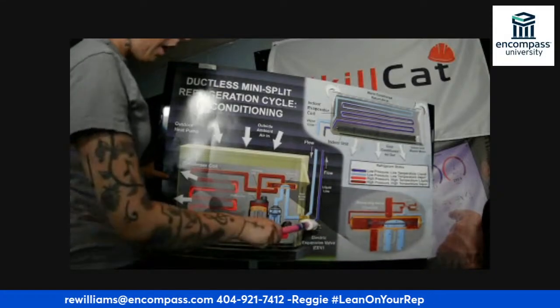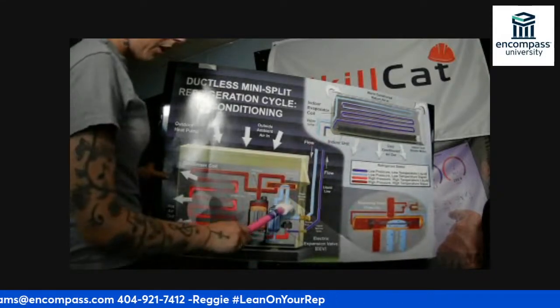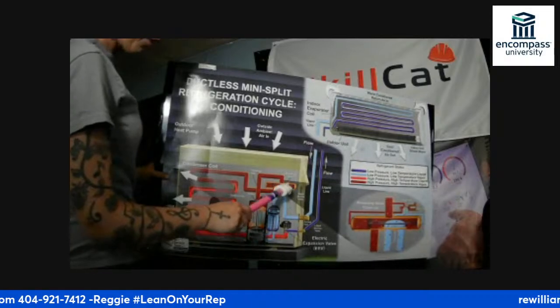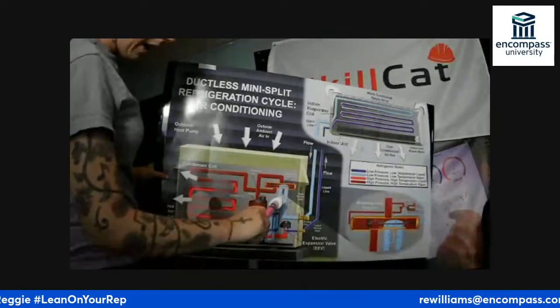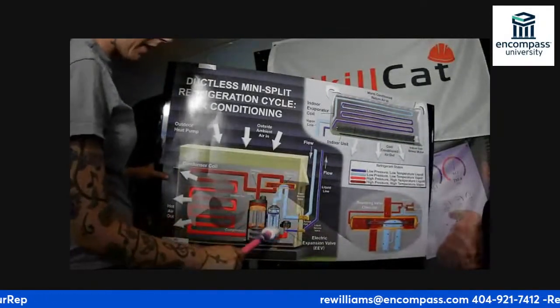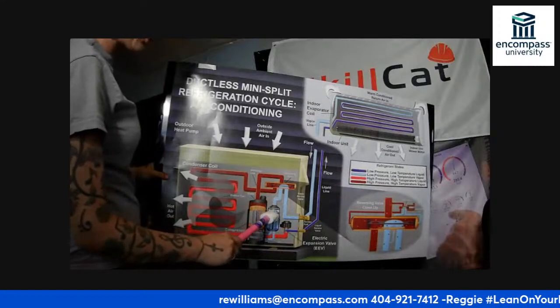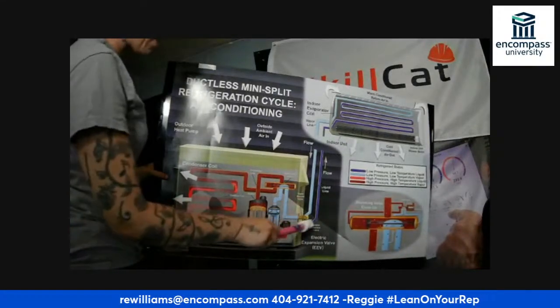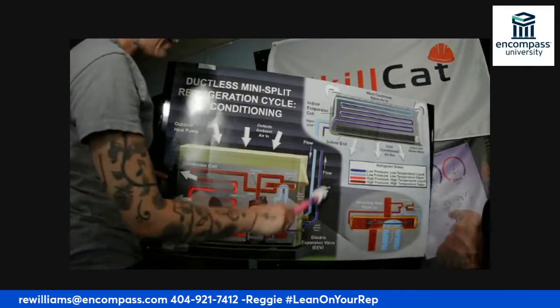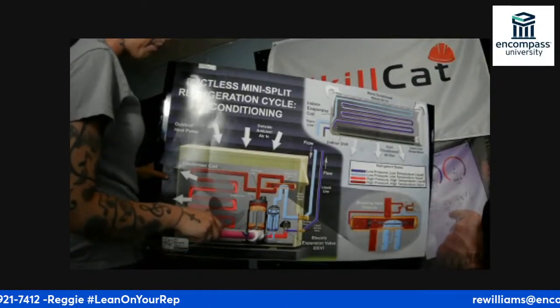So you're going to travel from the evaporator into the outdoor unit through the reversing valve. And then if we're in straight cool, it's going to come into the accumulator as that low pressure, low temperature vapor. Oh, we're coming out that way. Sorry, we're coming in this way. Okay, so when we're coming in, we're going to go to the compressor as a vapor. Again, compressor never sees liquid.